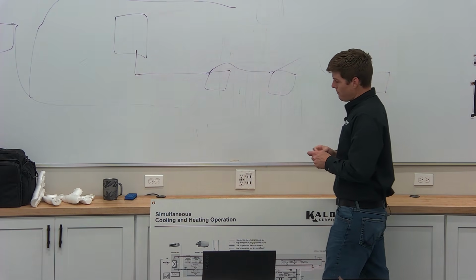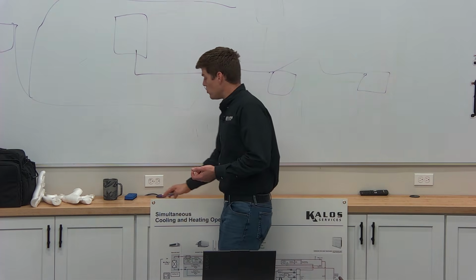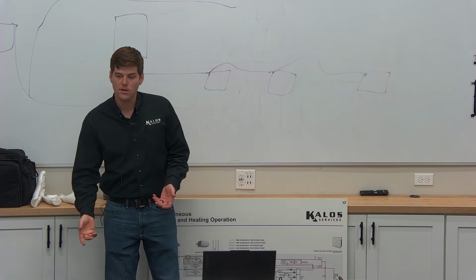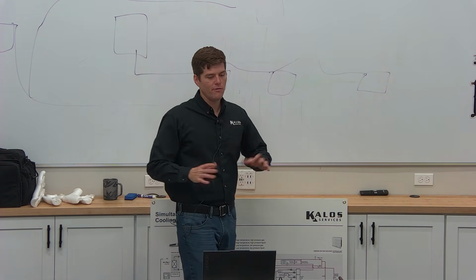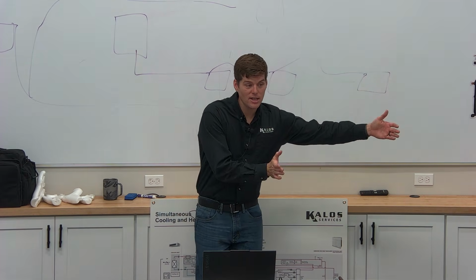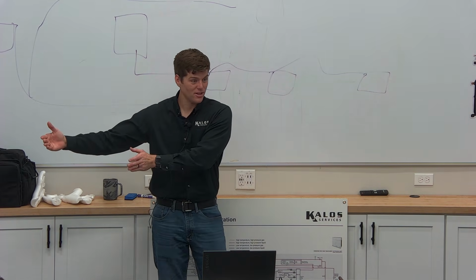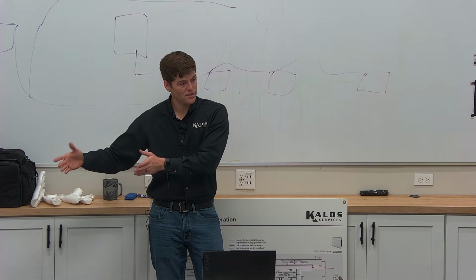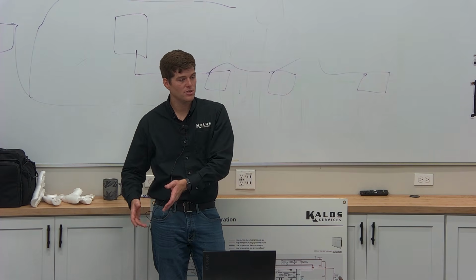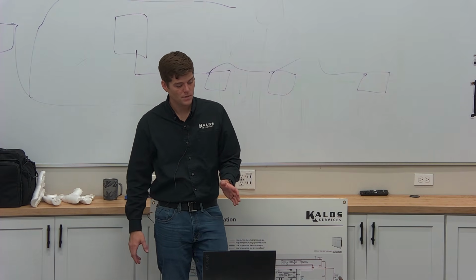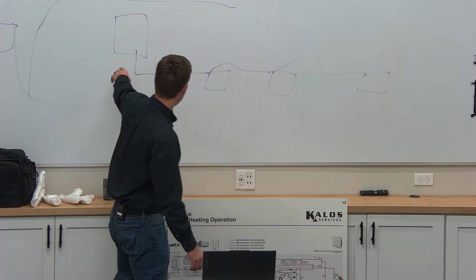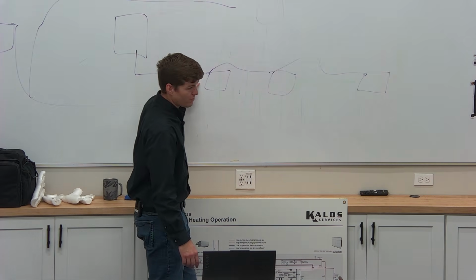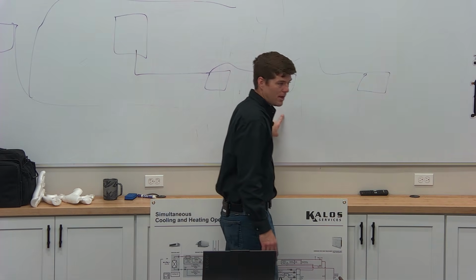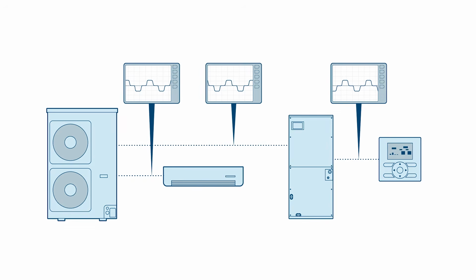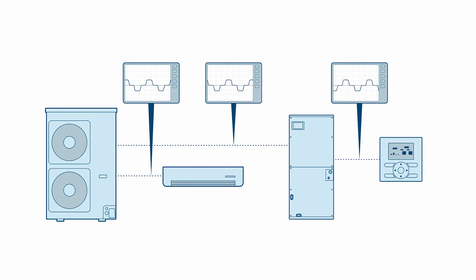VRF is different in the fact that we actually use one communication line. You're going to find that common thing in all VRF. It's all one refrigerant line set. It's all one communication line. Everything is daisy chained together. Star communication is not something that we do here. Which means that from my outdoor unit, I go to my indoor unit. And from this indoor unit, I go to my next indoor unit. From that indoor unit, I go to my next indoor unit, to my last indoor unit, and they all talk to each other on the same communication line back to the outdoor unit.